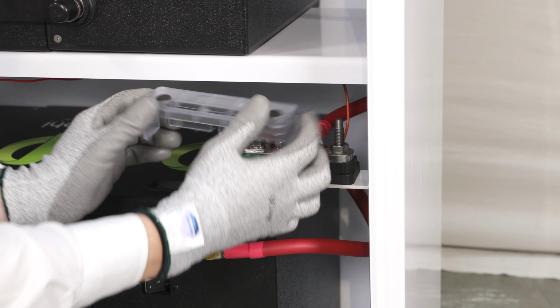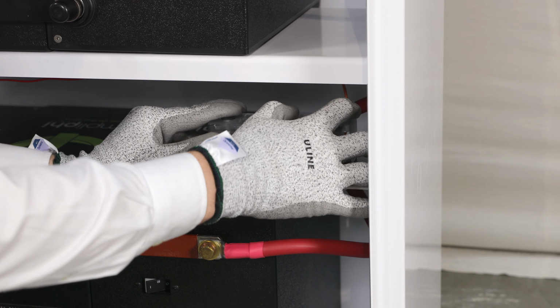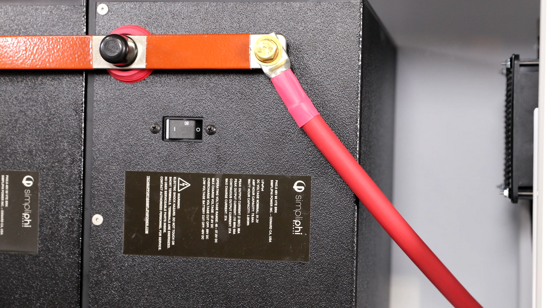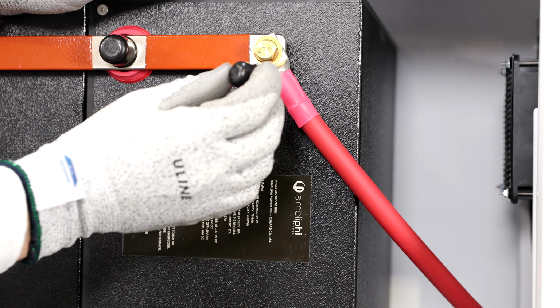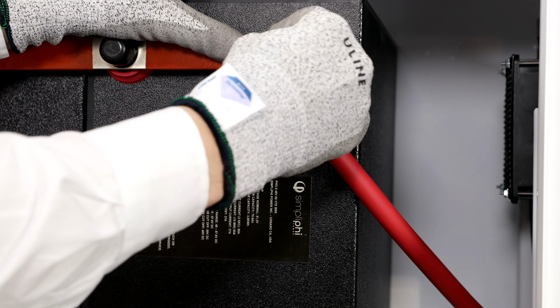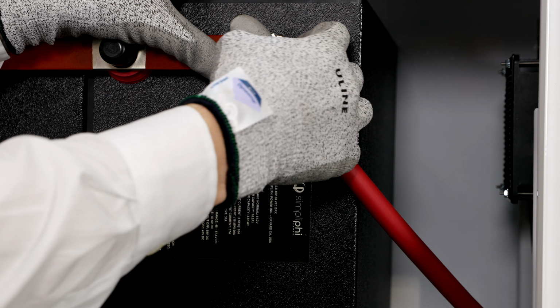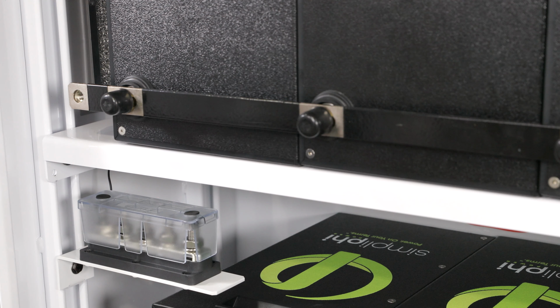Replace the plastic covering over the 5-point terminal block that was removed earlier. After securing the lug to the bus bar, place the black bolt caps over the brass hex bolts. Repeat the process for the negative terminals and 5-point terminal block. Prepare the 5-point terminal block for landing the cabling.